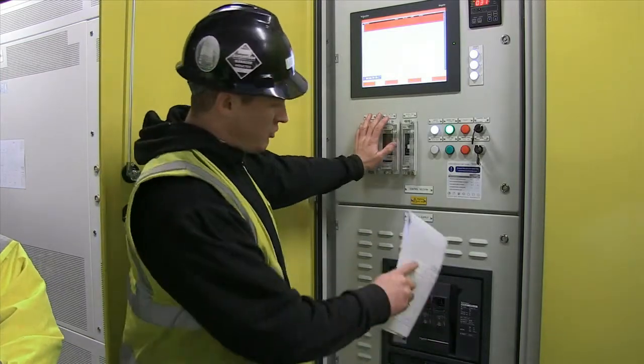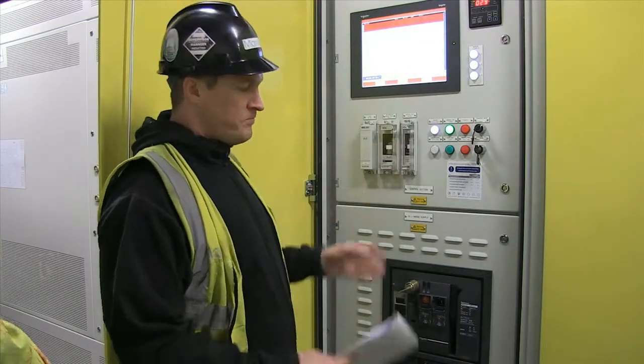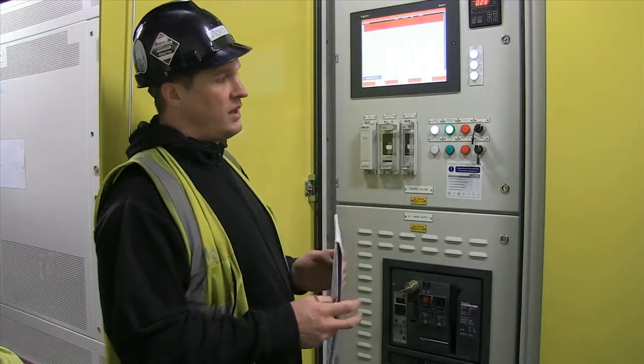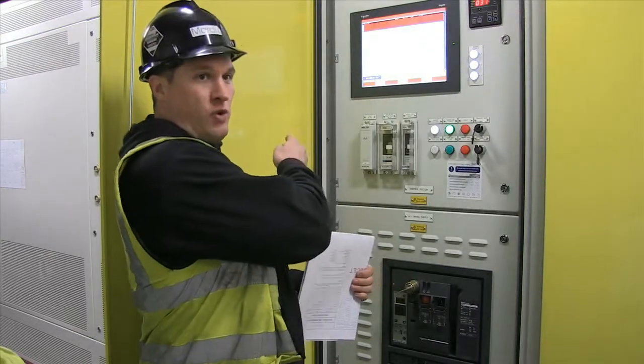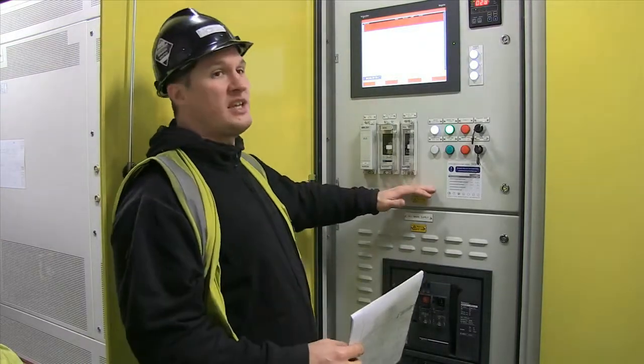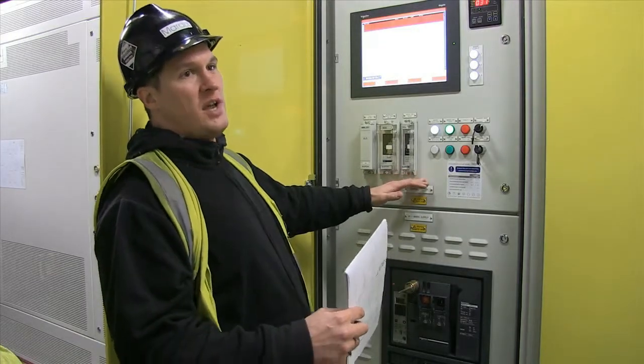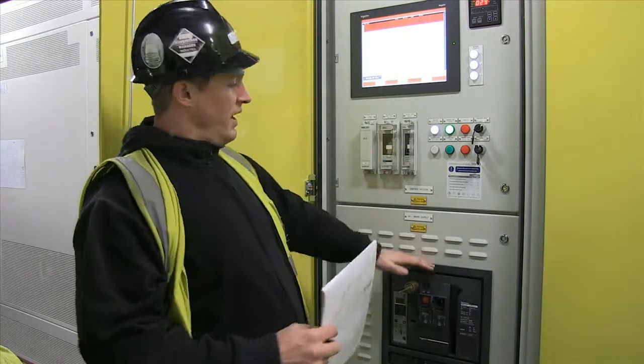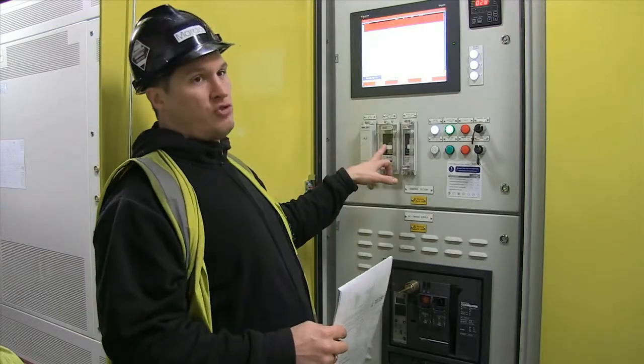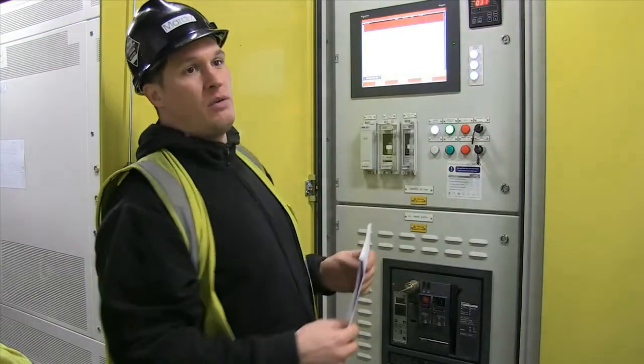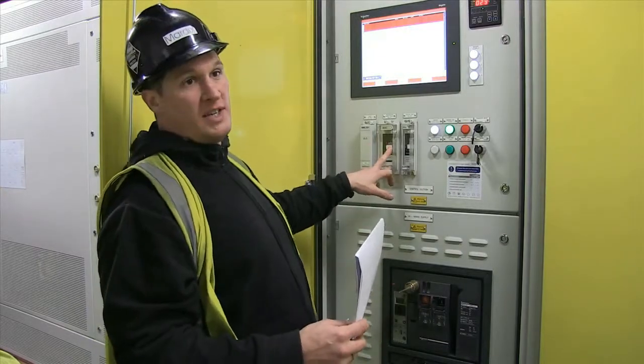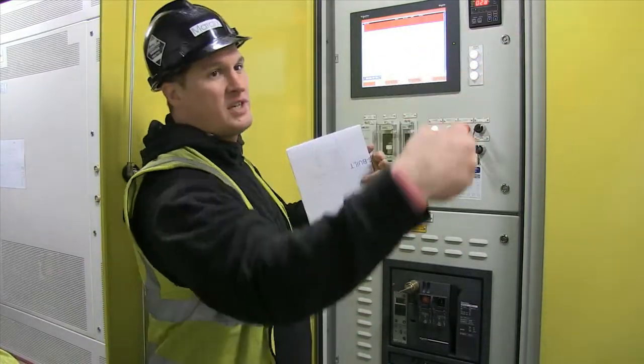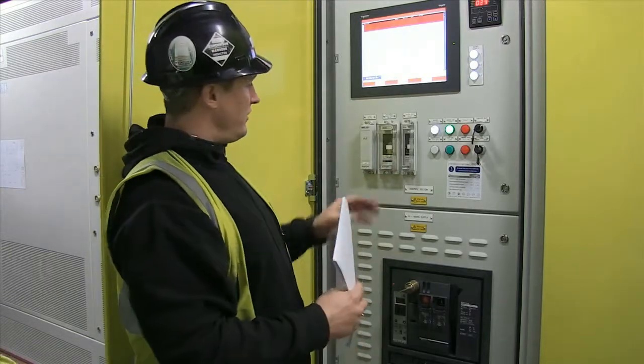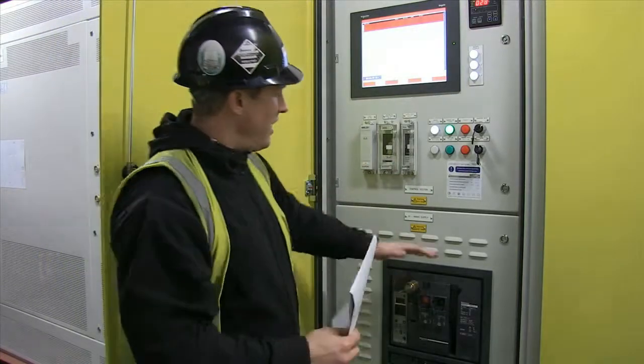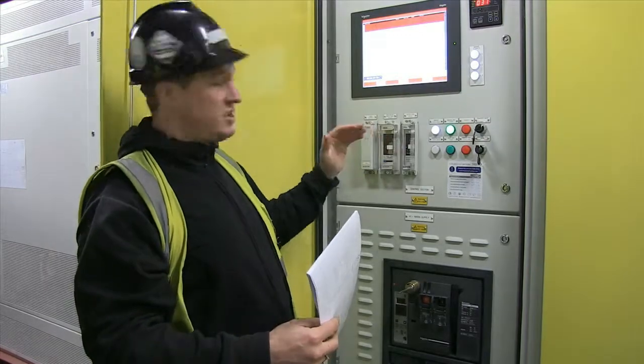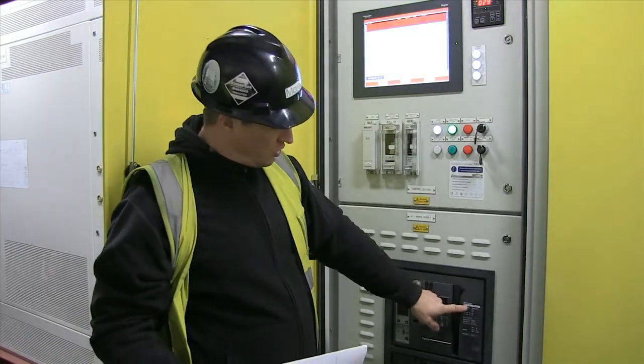Moving up, talking about tripping this breaker, the restricted earth fault. Now what that will do is give you protection between the transformer and the top of this breaker, or rather the CTs of the breaker. So if there's earth leakage anywhere between the transformer and this mains incomer, it will be sensed by the restricted earth fault relay. If it's any further down, it doesn't matter because it will see the current go through the CTs here, but also see it come back through the CTs through the neutral earth link. So if there's a fault between the transformer and there, it's picked up by the restricted earth fault, and it's set to 10%, which is 2,500 amps.